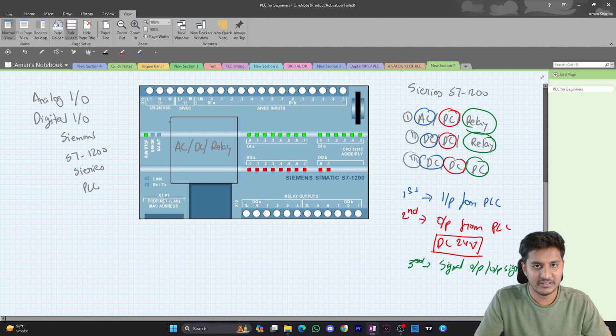So let's understand this PLC. Here you can see we have a 120 to 240 volt AC input. Then we have the output which is 24 volt. In some PLCs you have to outsource the 24 volt DC output, but most PLCs have an SMPS, switch mode power supply, which converts the supply to 24 volt DC. So the supply can be either AC or DC, and it will get converted to 24 volt DC.